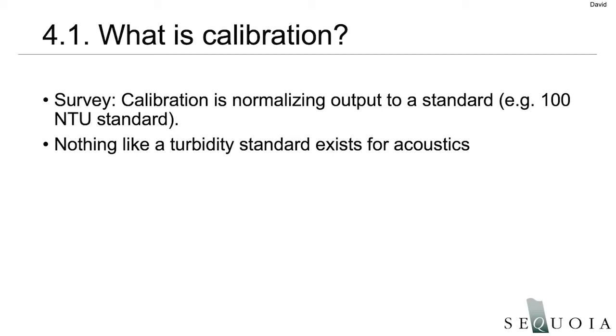Yeah, and that touches on one of the comments that was raised from the survey, because calibration has two different answers. One is that calibration is normalizing the output of a turbidity sensor to some turbidity standard, for example, 100 NTU. But there is no turbidity standard that exists for acoustics. That's really important to realize. So there's nothing really to standardize against except actual particle concentrations.